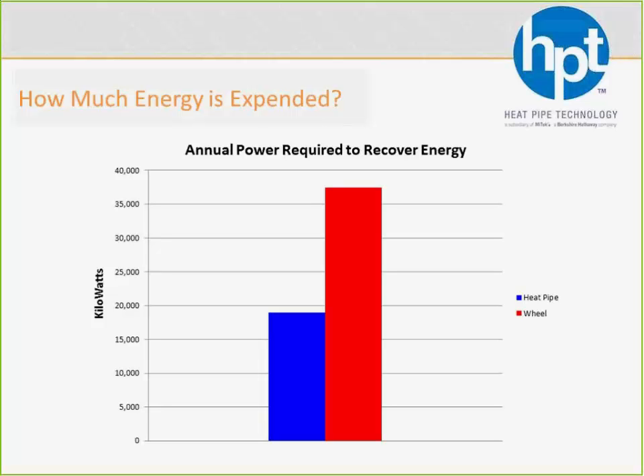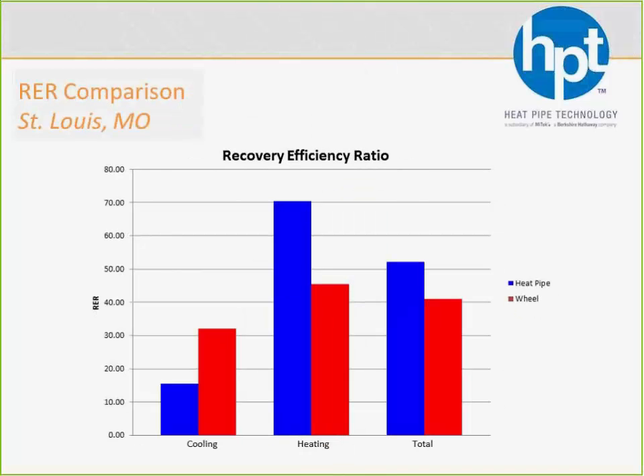So if the RER is the BTUs per hour divided by the watts, or basically the first slide divided by the second slide, you'll find that in the cooling season, we're still behind because we're not recovering latent heat. So anytime that we're not recovering latent heat and a wheel is, we're not only going to be further back from a BTU standpoint, but we're going to be further back from an efficiency standpoint.